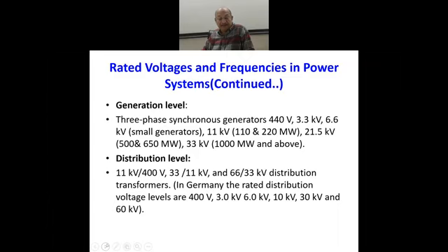One thing, the generators we are talking about are nothing but synchronous machines, synchronous generators. Synchronous machines have one synchronous speed, and a synchronous machine can be used either as a generator or as a motor. Such synchronous machines with power ratings of 110 to 220 megawatt generate power at 11 kV, whereas when we go to the larger generators, 500 and 650 megawatt, the power is generated at 21.5, you can say 22 kV level.